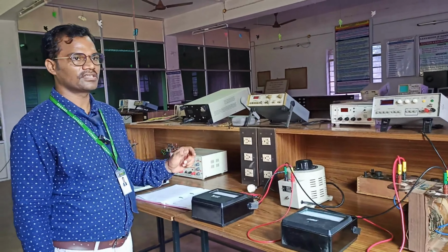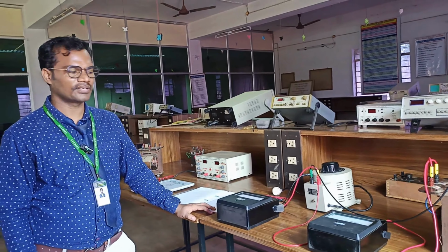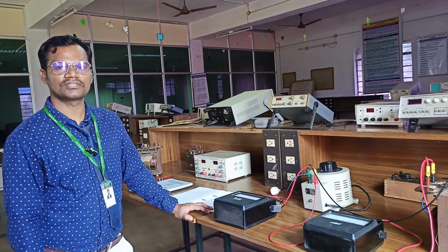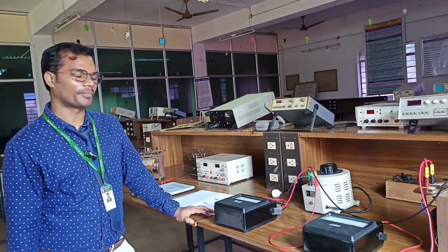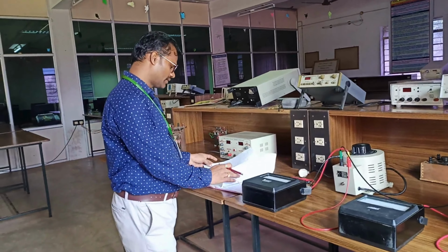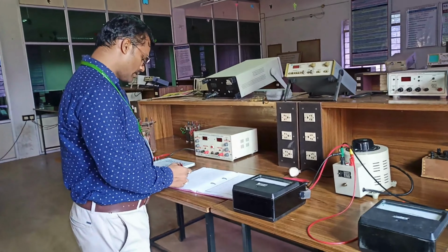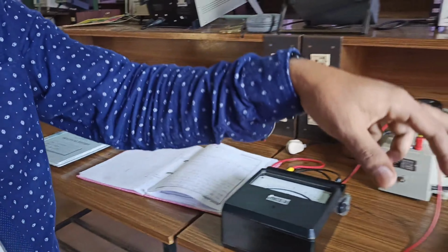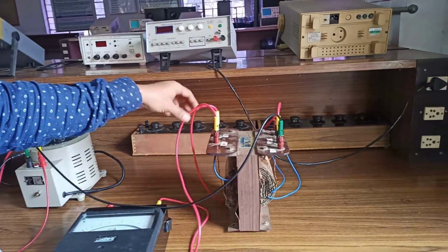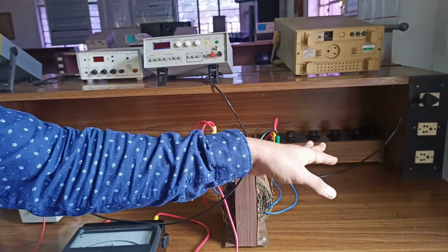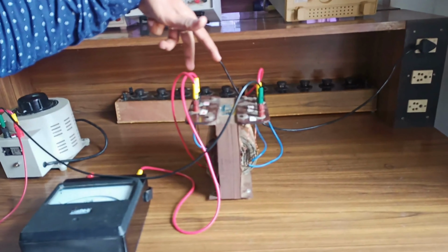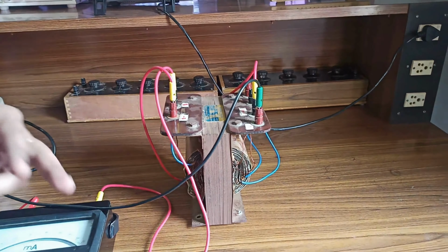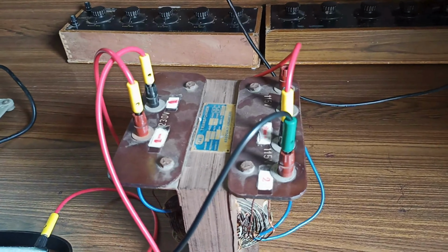So in the previous series additive we calculated Z1, and by series subtractive we calculated Z2. Then the mutual inductance is (Z1 minus Z2) divided by 4 omega. Then we are going to calculate the mutual inductance offered by this transformer. You can see here this is the primary of the transformer, this is the secondary of the transformer, but we coupled them in series additive as well as series subtractive in nature. This is the process of giving the connections.